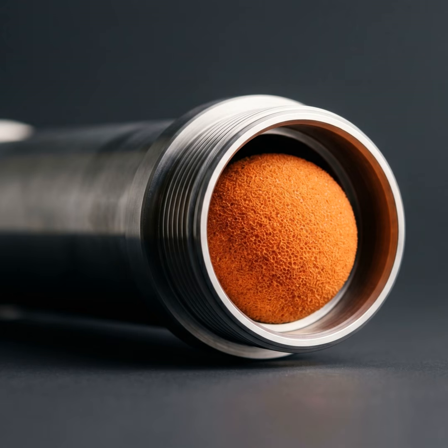Right. So they don't just float freely through the center of the water column doing nothing. No, they have to squeeze. They have to actively squeeze through the metal piping. And as they squeeze through, pushed by the immense natural water pressure of the system's own pumps, they act as physical squeegees. It's so smart. They physically wipe away all the microscopic mineral deposits, the calcium carbonate, the biological biofilm, before it ever gets a chance to bake on and crystallize into that hard rock.